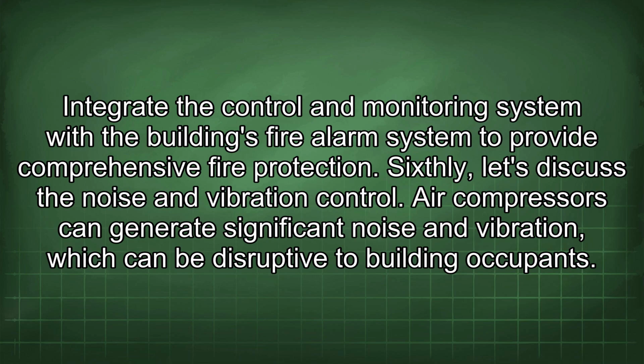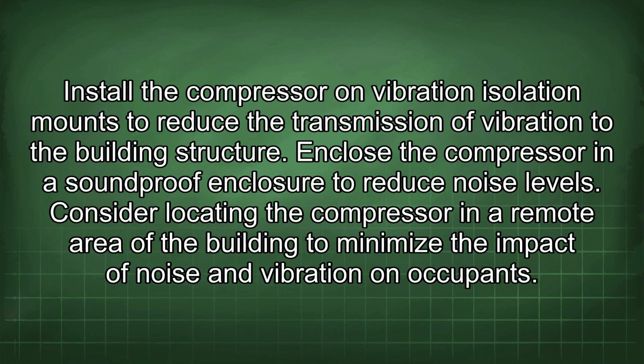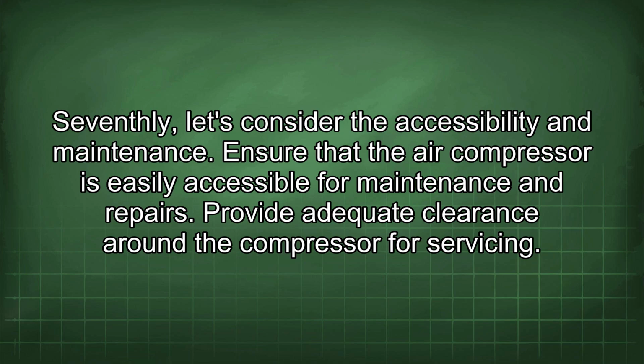Sixthly, let's discuss the noise and vibration control. Air compressors can generate significant noise and vibration, which can be disruptive to building occupants. Install the compressor on vibration isolation mounts to reduce the transmission of vibration to the building structure. Enclose the compressor in a soundproof enclosure to reduce noise levels. Consider locating the compressor in a remote area of the building to minimize the impact of noise and vibration on occupants.